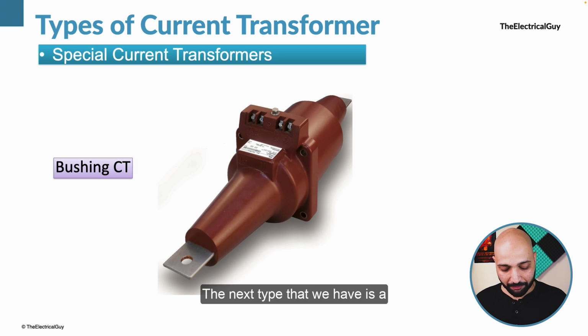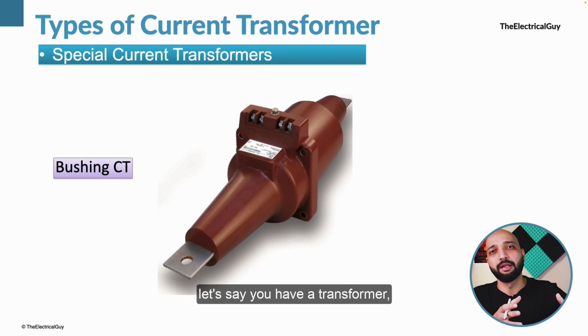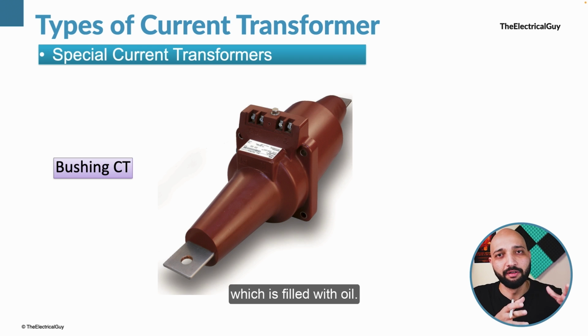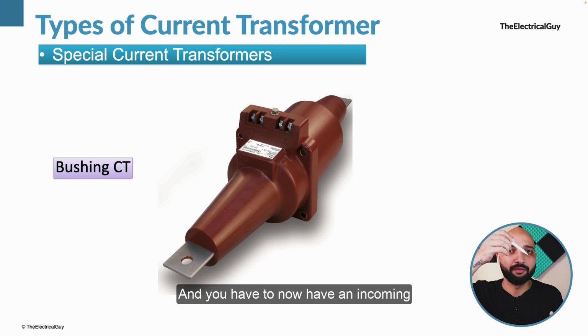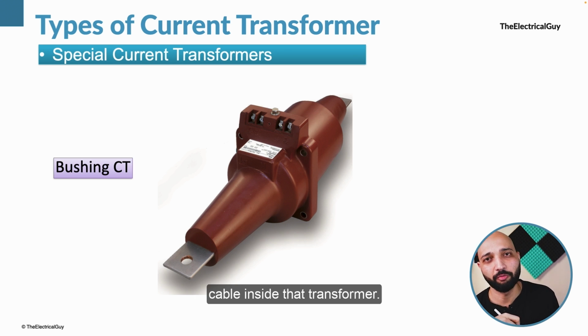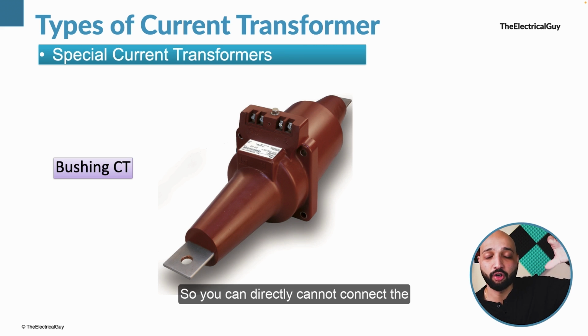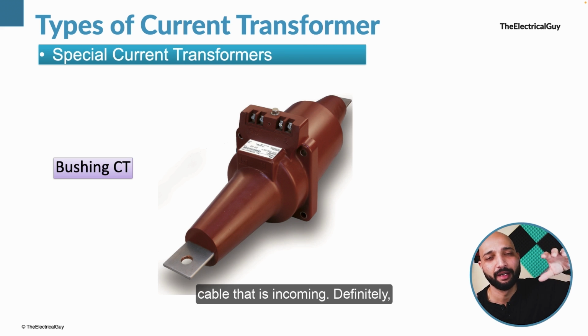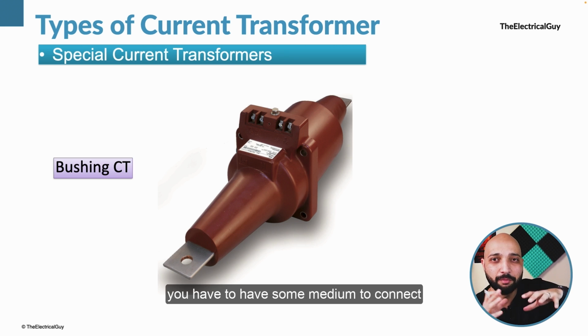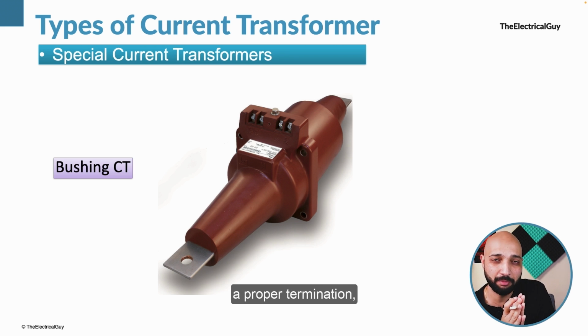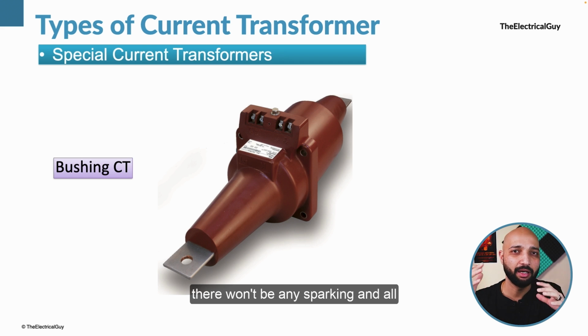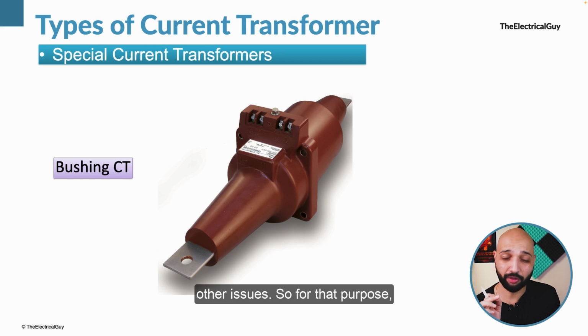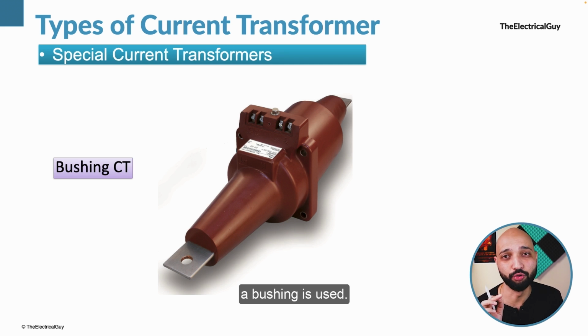The next type that we have is a bushing current transformer. If you don't know what a bushing is, let's say you have a regular power transformer, which is filled with oil, and you have an incoming cable inside that transformer. You cannot directly connect the incoming cable. You definitely have to have some medium to connect it, so that there will be a proper termination, and there won't be any sparking and all other issues. So for that purpose, a bushing is used.